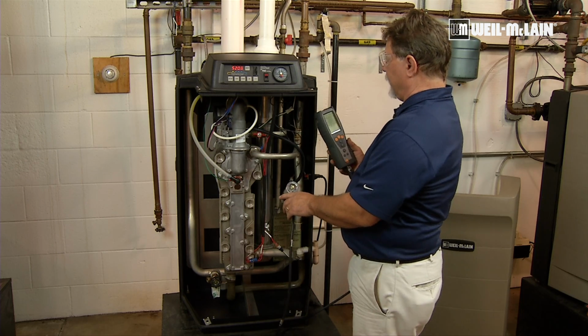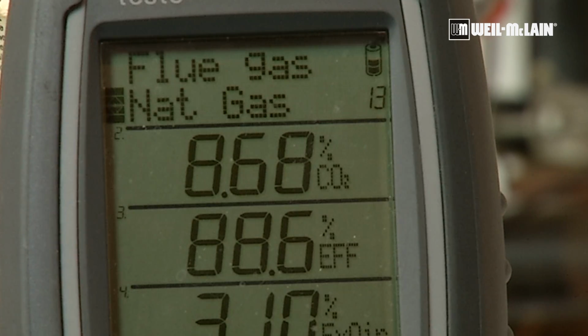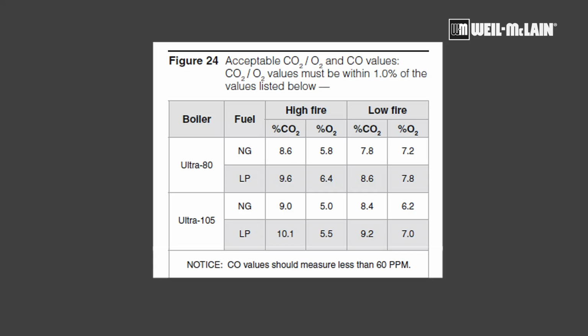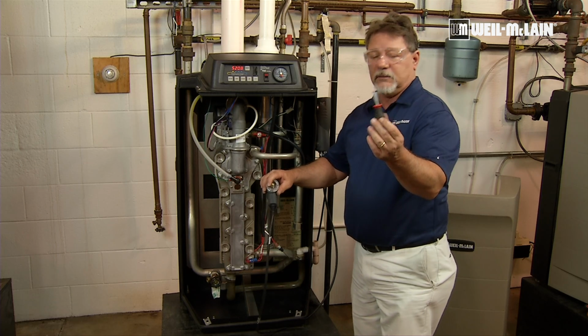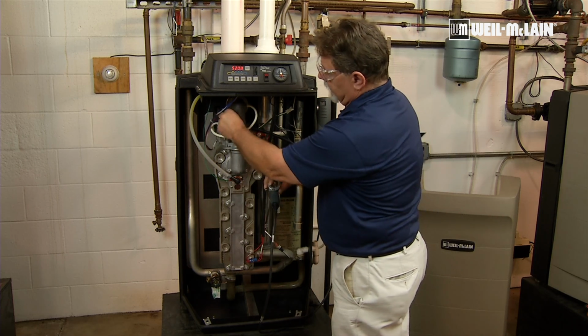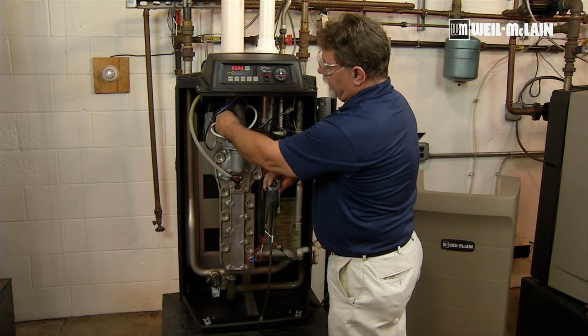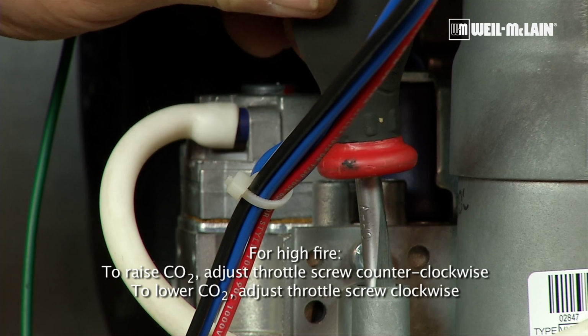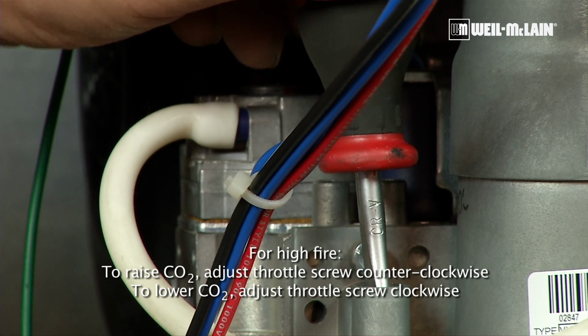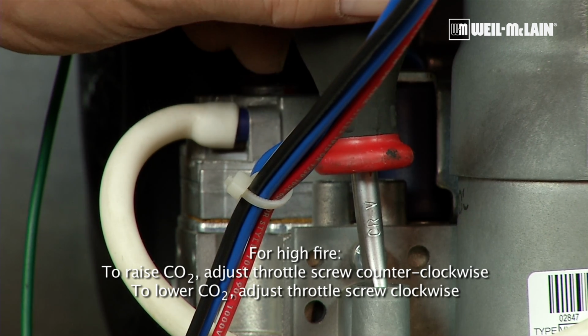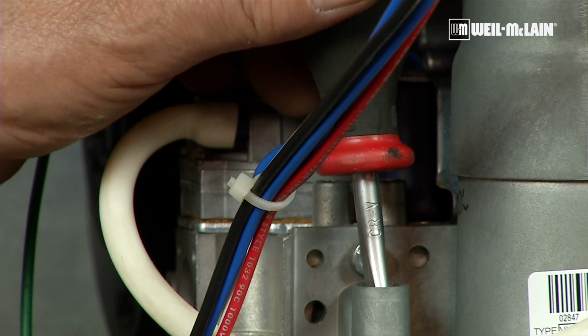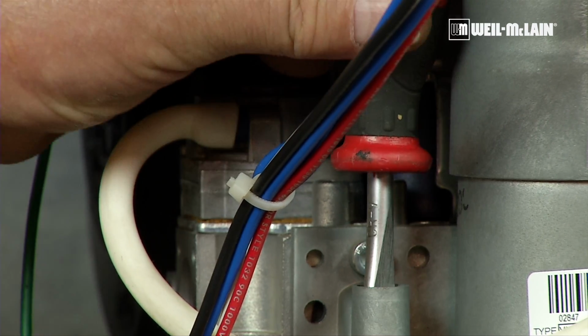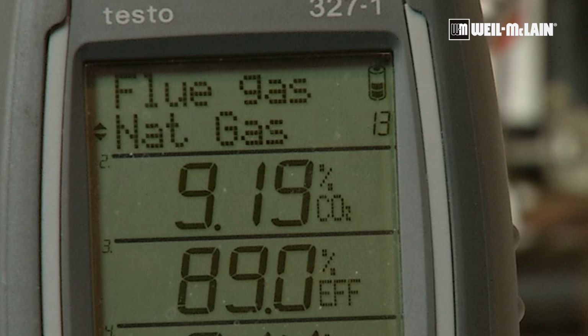All right, so my high fire combustions, my analyzer is reading 8.6, which is acceptable, but it's on the low end. We need a small straight blade screwdriver, insert it into the throttle screw, and we want to go counterclockwise on that screw to increase the CO2. If you go clockwise, you're closing the throttle screw and your CO2 will fall. The meter is stabilized out at 9.19%, and I'm happy with that.